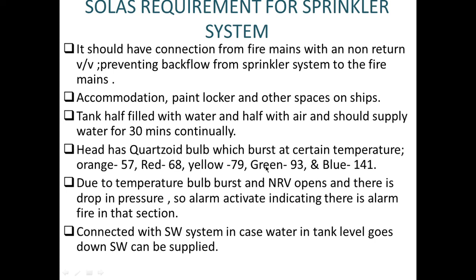Now you must be having a question: how does the alarm activate, that yes, the sprinkler has started? There has to be an audio and visual alarm. How does this activate? Due to the rise in temperature, the bulb, which is designed for a certain temperature, bursts. The NRV, the non-return valve, opens, and there is a drop in pressure. The line will have a drop in pressure, which is associated with a system. This drop in pressure is sensed and taken into account, and it gives an alarm in the system.